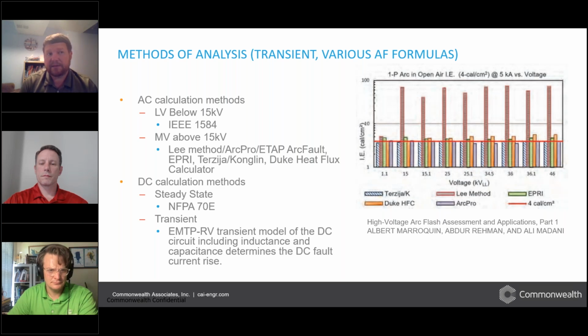But please note that the medium voltage arc flash generally isn't the major concern here. The major concern on the AC side is on the inverter terminals or the transformer low sides, which are low voltage, which are calculated with the IEEE 1584 methods, and the DC methods, which are calculated with NFPA 70E.